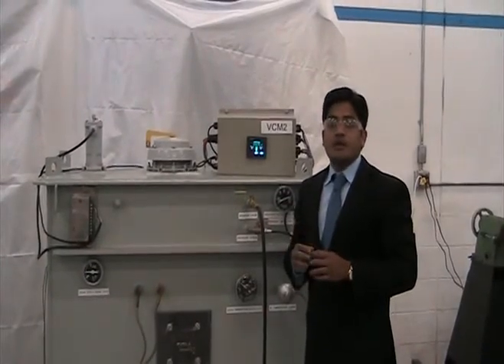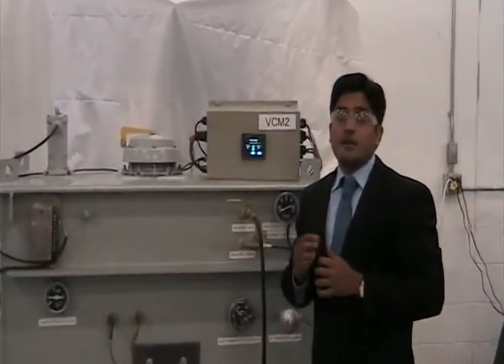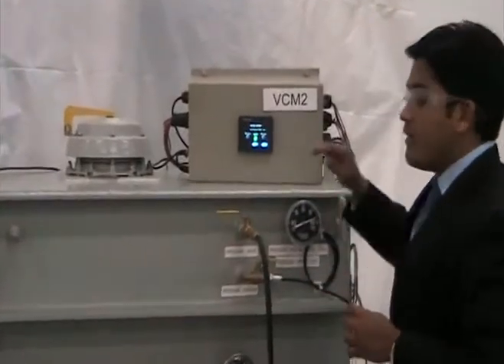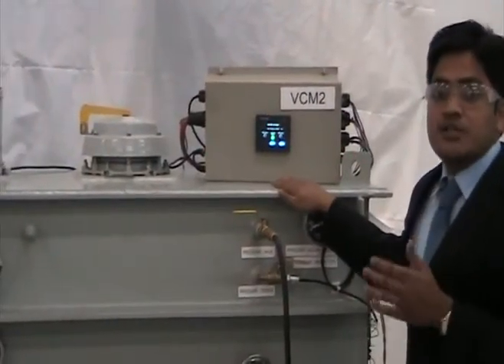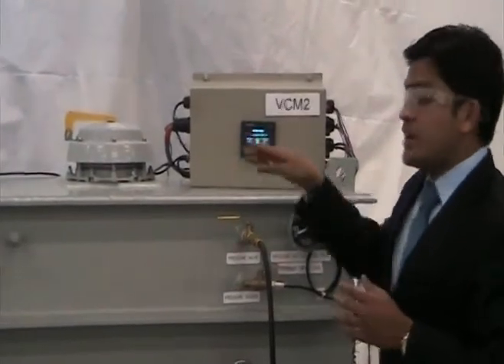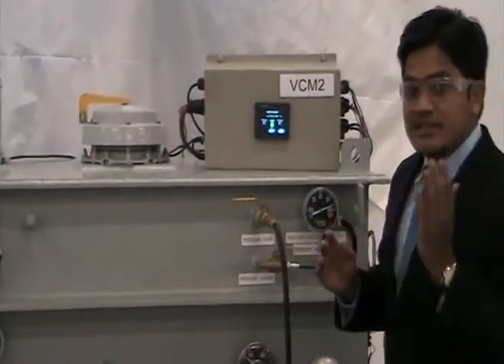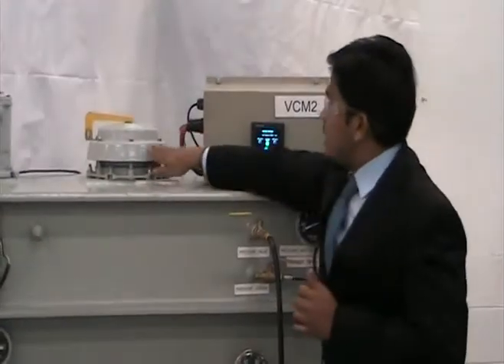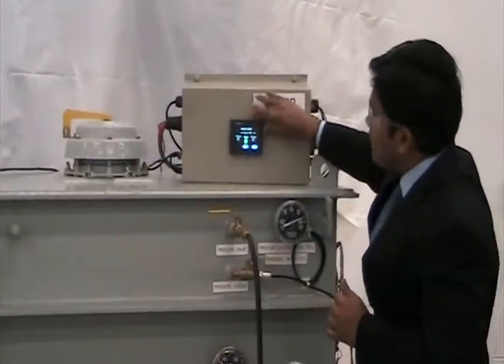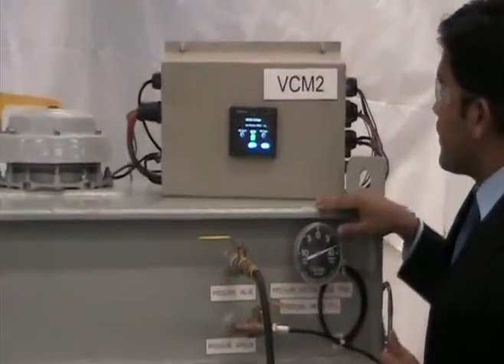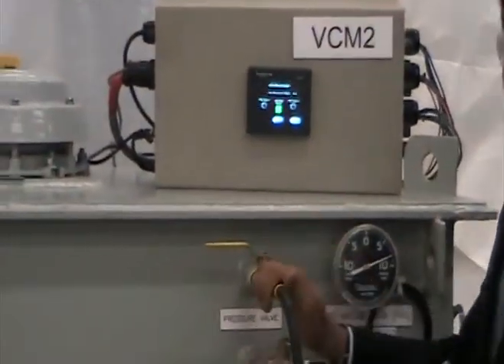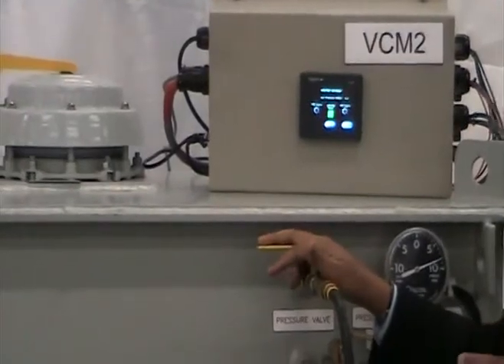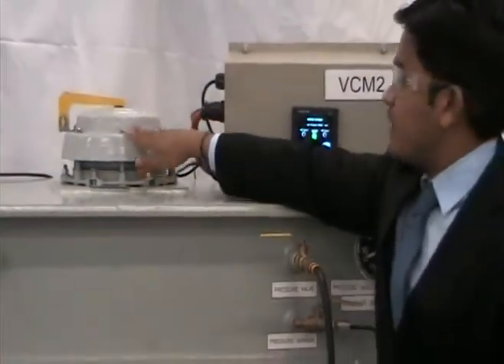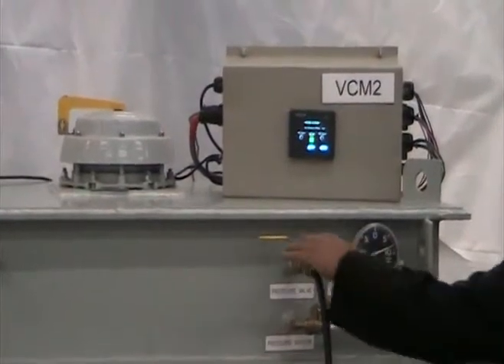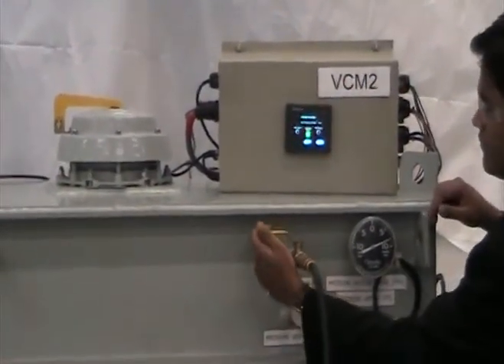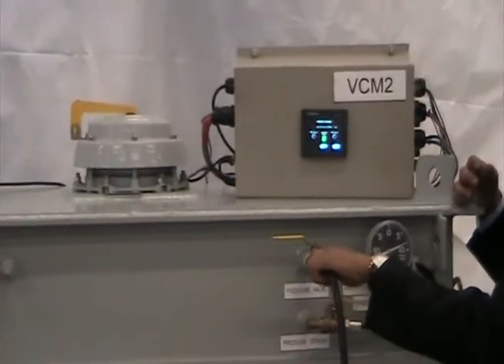Now I will show you how VCM2 can detect the operation of pressure relief device. When the pressure inside the transformer goes more than 10 psi, the pressure relief device operates and it releases the pressure. When the PRD is activated, the alarm on the VCM2 screen is visible. Now I will simulate the pressure to more than 10 psi to activate the pressure relief device. I will use this air hose to change the pressure.